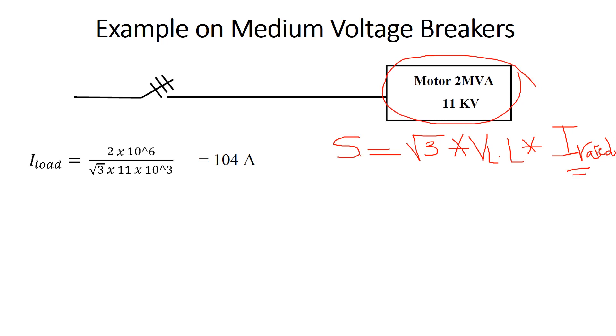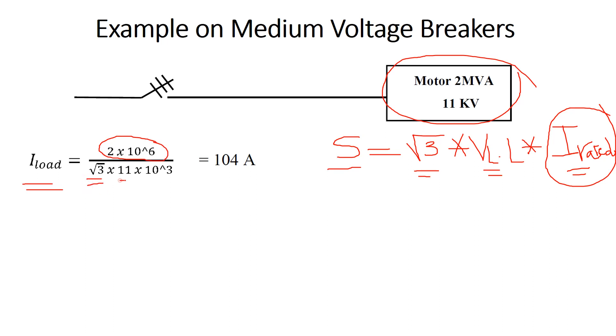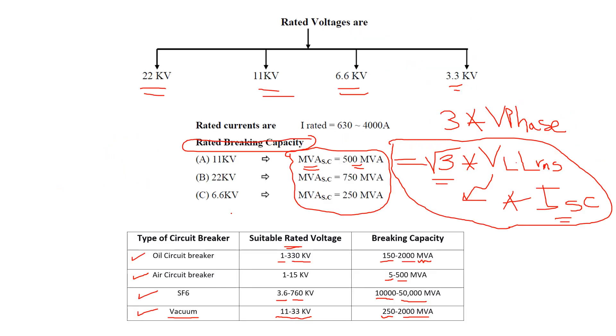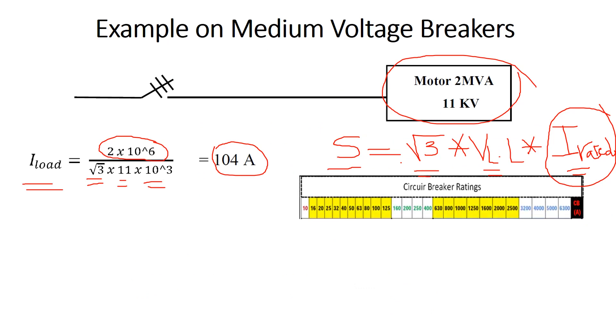Note that the rated current relates to rated power, while the breaking capacity relates to short circuit current. The rated current of the motor is: I = S / (√3 × V_LL) = 2 MVA / (√3 × 11 kV) = 104 A. Since medium voltage circuit breakers are rated from 630 A to 4000 A, we select the 630 A rating.